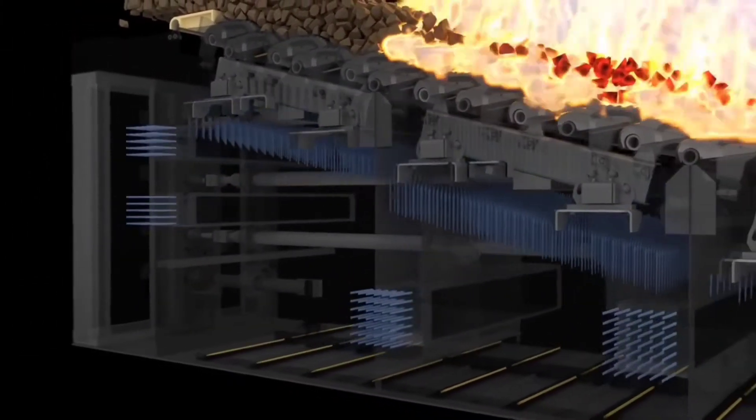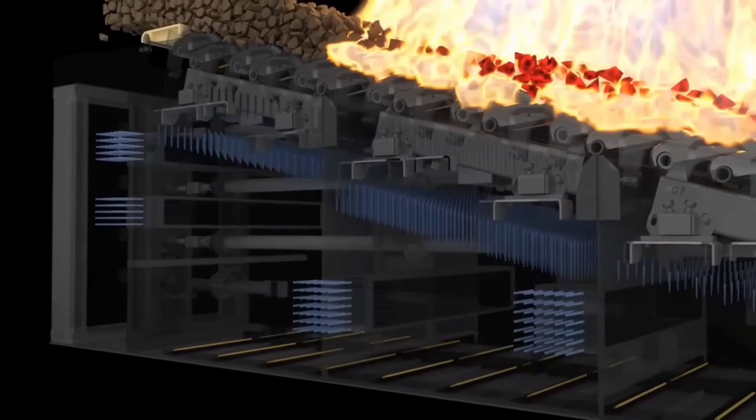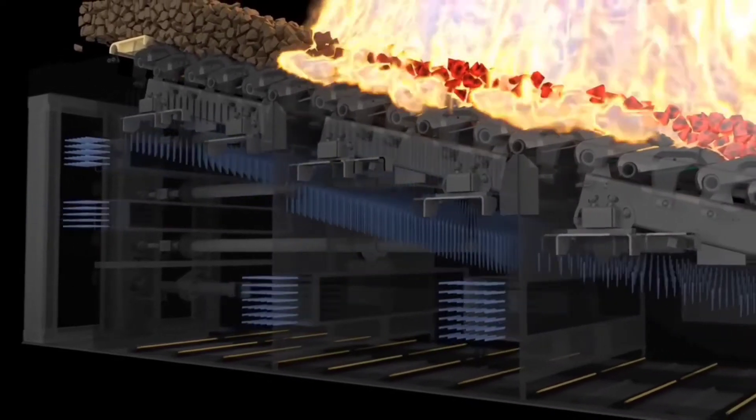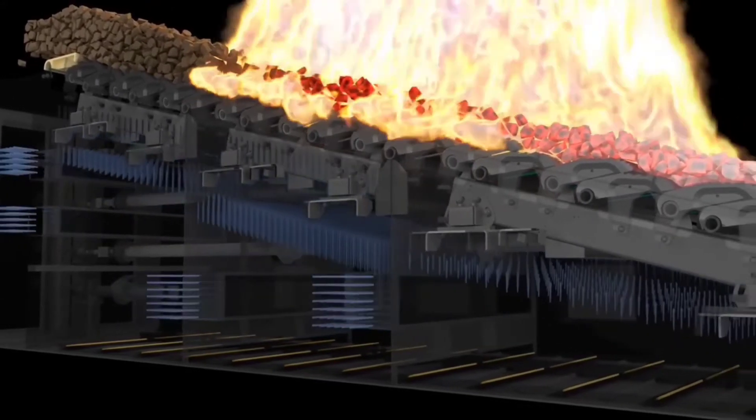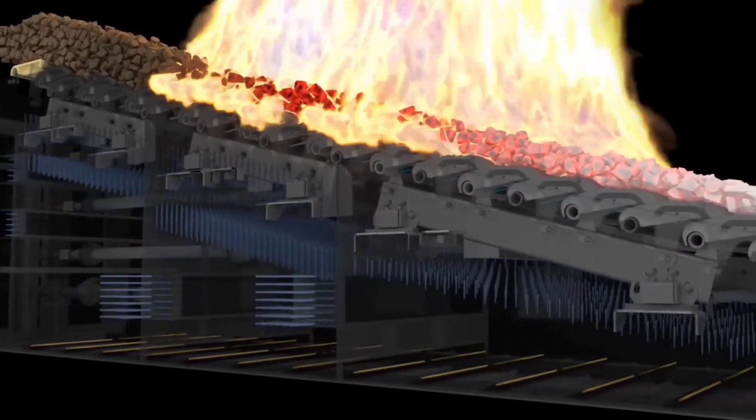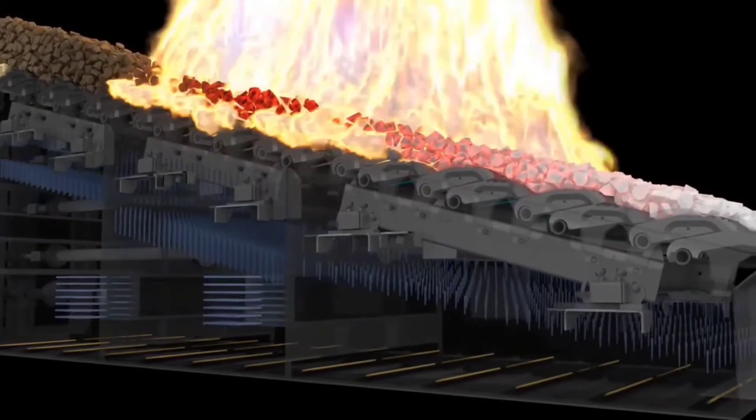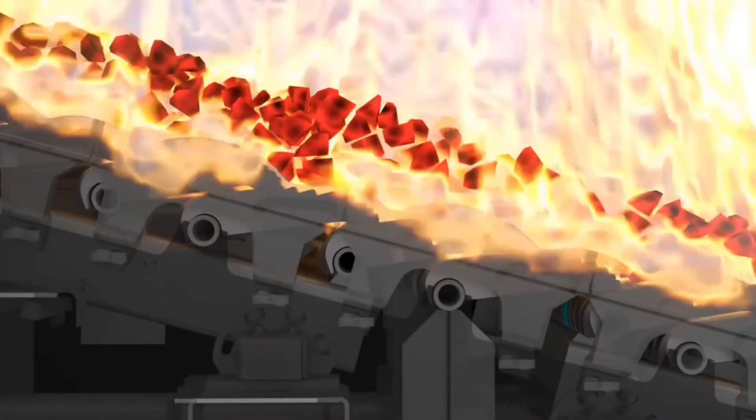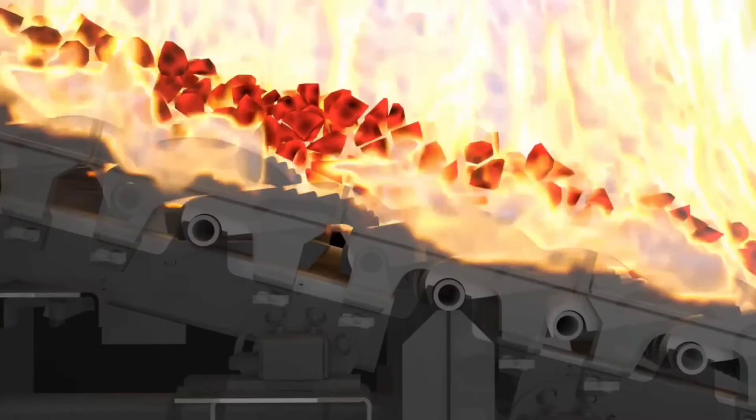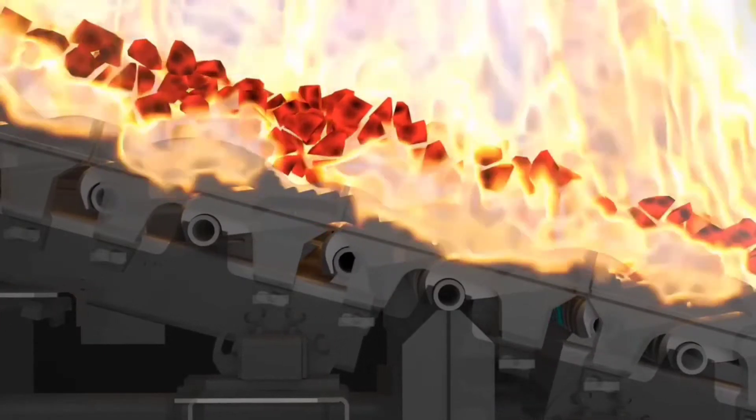Each section of grate consists of a hydraulically driven trolley and independent air supply. The speed of each trolley and its respective air control ensures the most efficient air to fuel ratio. Reciprocating motion gives toppling action to the fuel particles, ensuring complete combustion.